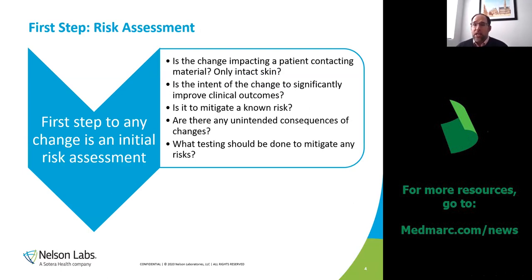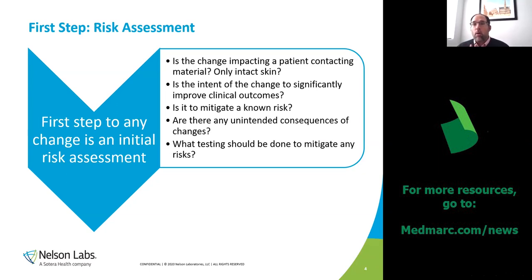The first step to any change is a risk assessment. ISO 10993-1 has gone through major changes in the last six or seven years. In 2018, they came out with a new version that was more heavily focused on a risk-based approach. We're trying to get away from a checkbox testing mentality where you just do all the testing without thinking about your device's risks. We're forcing the industry into more of a risk-based approach. A new draft just came out last month with drastically proposed changes to make it even more risk-based. So the first step of any change is always a risk assessment.